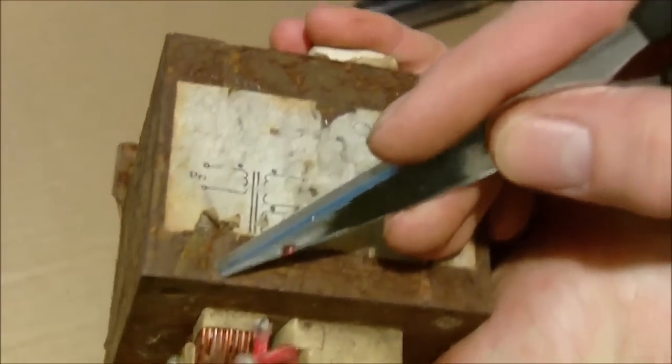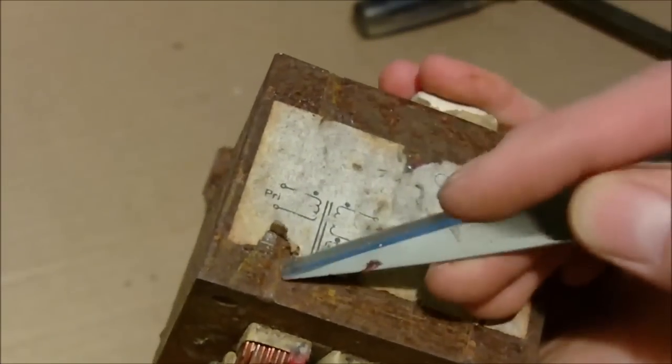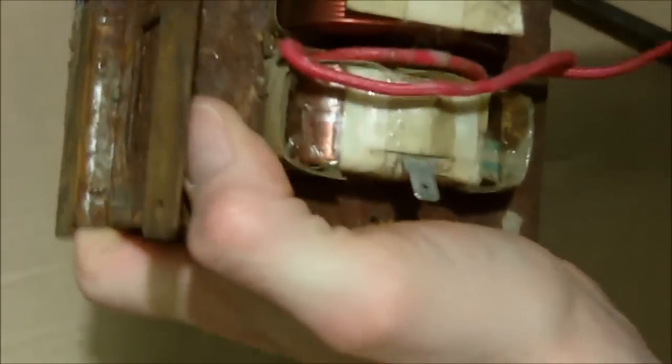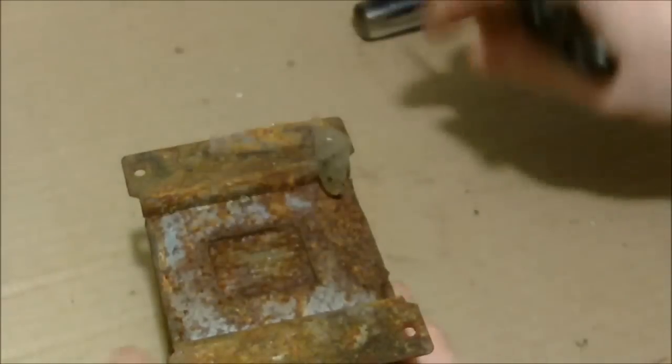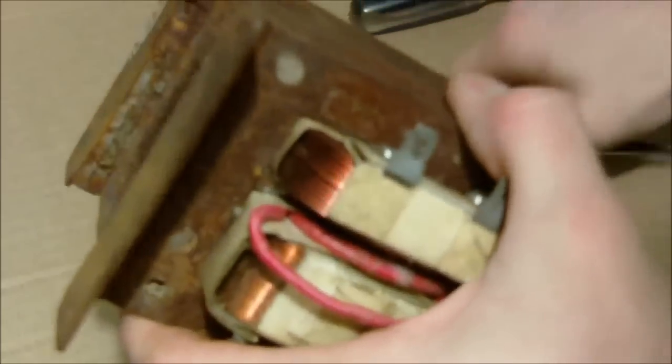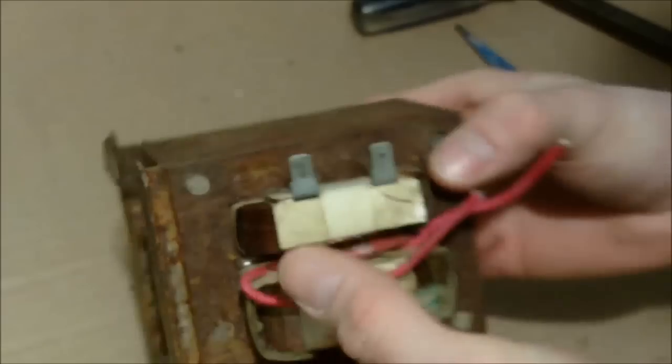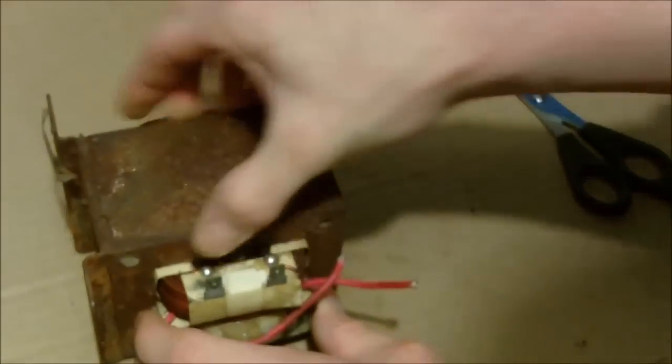This transformer, only one end is open, only this end will come off. So what you're going to have to do is cut the weld across here. You can see there's a weld right here, you have to cut that weld off. Then you're going to have to take this bottom piece off as well. You can see there's a weld here, so you have to grind this weld off. Once you've done that, then this piece, this whole piece here, will come off.